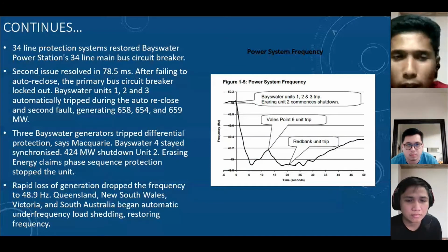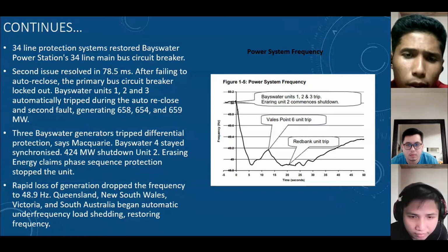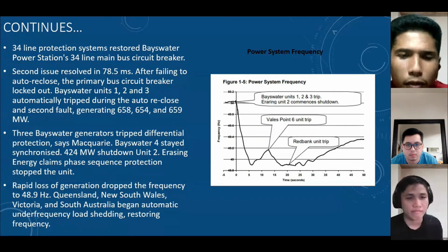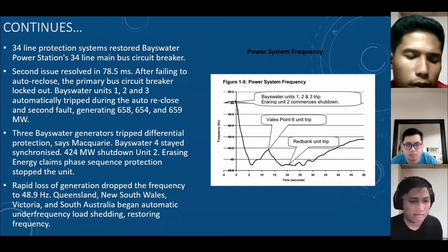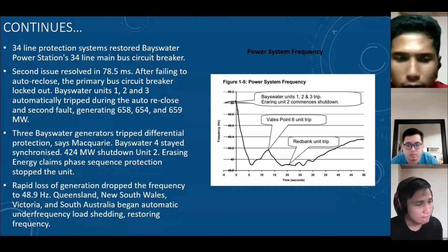Bayswater units 1, 2 and 3 automatically tripped. Three Bayswater generator differential protections operated. Bayswater 4 stayed synchronized. The rapid loss of generation dropped the frequency to 48.9 Hz.